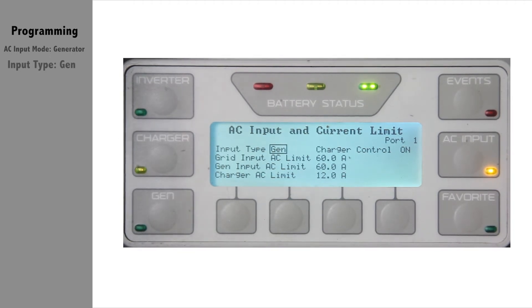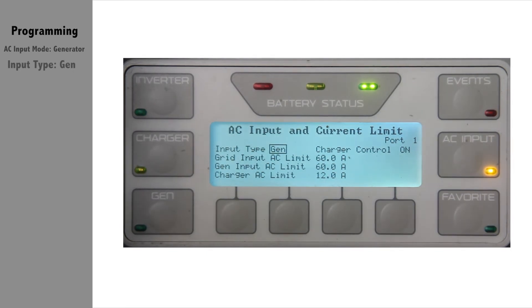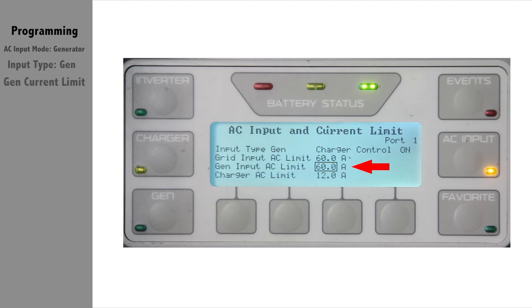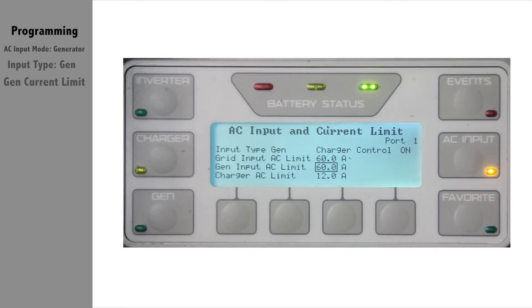If you are experiencing nuisance disconnects for overloading the generator, then you may need to reduce the amount of current you draw from it. From the same screen, scroll down to gen input AC limit and drop the current to the recommended settings from your generator manufacturer.